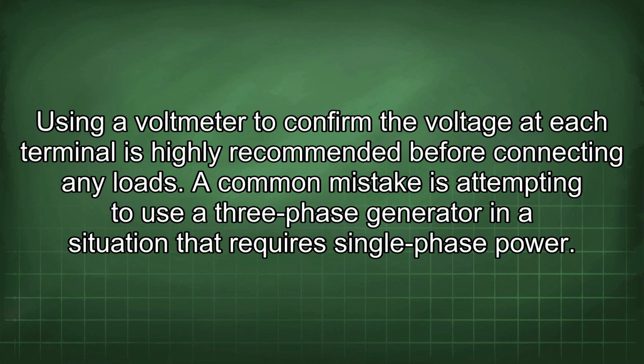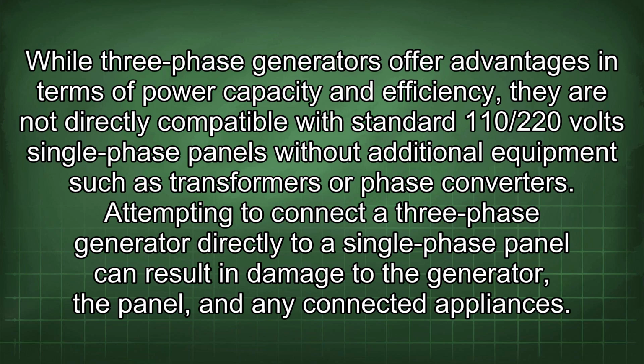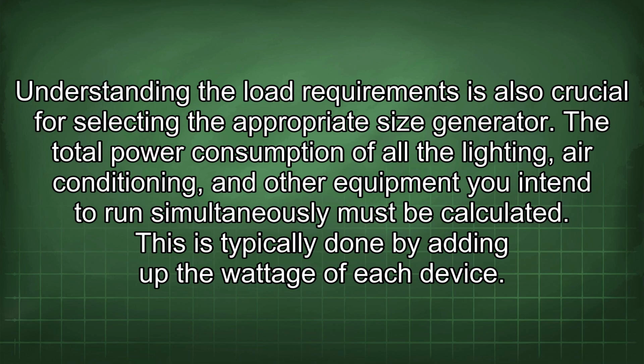A common mistake is attempting to use a three-phase generator in a situation that requires single-phase power. While three-phase generators offer advantages in terms of power capacity and efficiency, they are not directly compatible with standard 110/220 volt single-phase panels without additional equipment such as transformers or phase converters. Attempting to connect a three-phase generator directly to a single-phase panel can result in damage to the generator, the panel, and any connected appliances. Understanding the load requirements is also crucial for selecting the appropriate size generator.